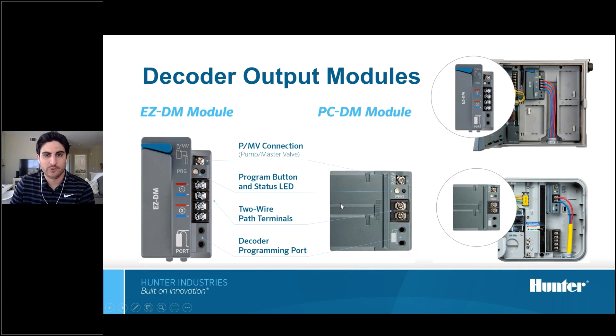Moving on to the decoder. Currently, we only offer a single station EZ1 decoder, but the EZ1 decoder does have enough juice, or electricity, in it to operate two Hunter solenoids at a single time. Obviously, we don't recommend doubling up your outputs because that puts some stress on the transformer or the controller, but ultimately, if you're in a pinch, say you've got a two-valve manifold and you need to wire up those two zones to come on simultaneously, there's enough electrical energy in these EZ1 decoders to snap two Hunter solenoids at a time without a threat of overamping a transformer. So a lot of flexibility being able to hook two stations to one output on the decoder, but we recommend just one station per decoder.